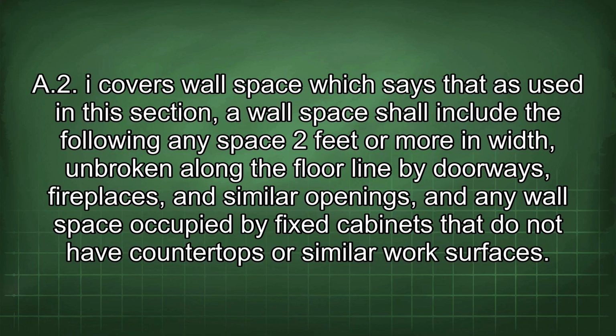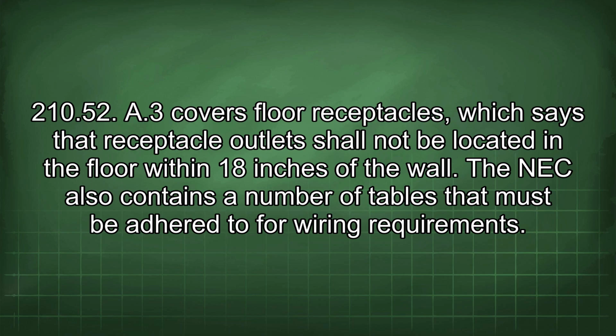210.52 A2 covers wall space, which says that as used in this section, a wall space shall include the following: any space 2 feet or more in width, unbroken along the floor line by doorways, fireplaces, and similar openings, and any wall space occupied by fixed cabinets that do not have countertops or similar work surfaces. 210.52 A3 covers floor receptacles, which says that receptacle outlets shall not be located in the floor within 18 inches of the wall.